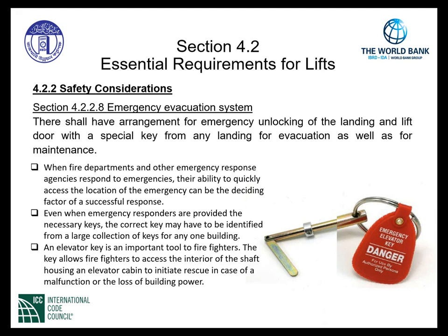Emergency evacuation system in section 4.2.2.8 indicates there shall have arrangement for emergency unlocking of the landing and lift door with a special key from any landing for evacuation as well as for maintenance. When fire departments and other emergency response agencies respond to emergencies, their ability to quickly access the location of the emergency can be the deciding factor of a successful response.